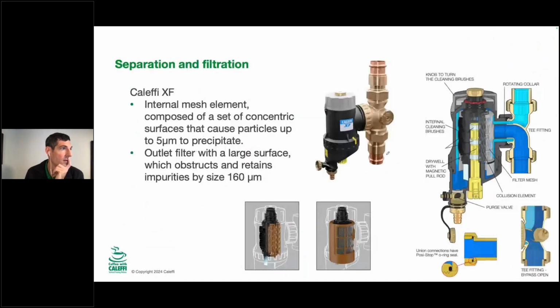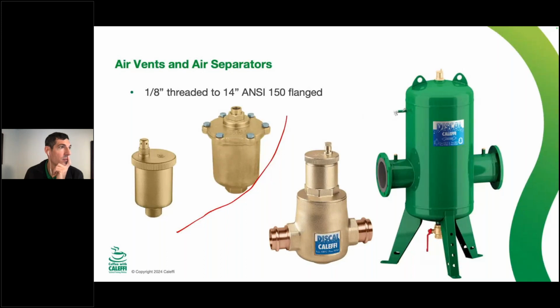We also had a question about the top here. So what is this at the top of an air separator? In these big commercial devices, it would take a long time to get all that air out through this 1/8 inch cap at the top, or smaller than that, through the top of the air vent. So this is a gooseneck that comes up into the device here. You could hook this up to a water heater hose, take that down to a floor drain, and you're going to allow air to come out at a much higher flow rate until you start to get a little bit of water.